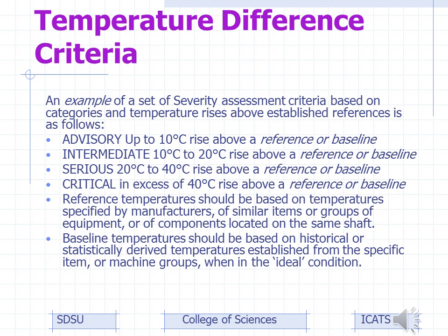Okay, temperature difference criteria is presented in the ISO standard, and as I said earlier, we do like this in particular as it is the base for most things that we do, at least that we've been involved with in the past, and for things I train people for. It states in the text, this is an example of the severity assessment criteria. I've known people that have used different criteria with higher temperatures in this, and I disagree with those. I think the ISO standard is well thought out, and for good reason.